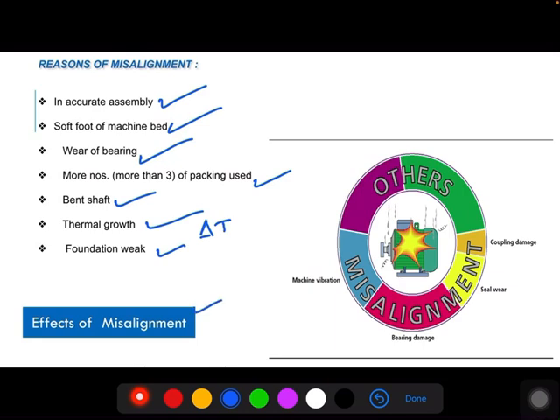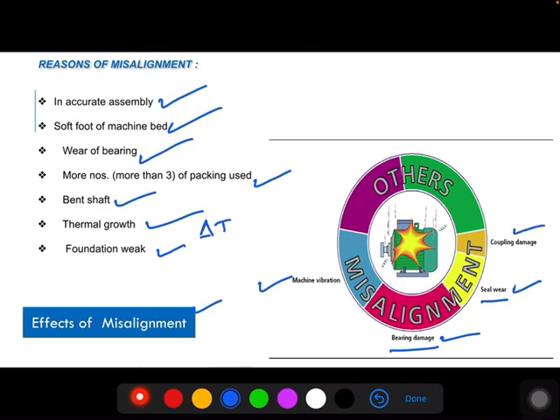If a machine is having misalignment, it increases the vibration of the machine. Because of this vibration, there will be bearing damage. Also, if the machine shafts are at an inclined condition, it results in seal wear and coupling damage. These are some of the defects caused by misalignment.